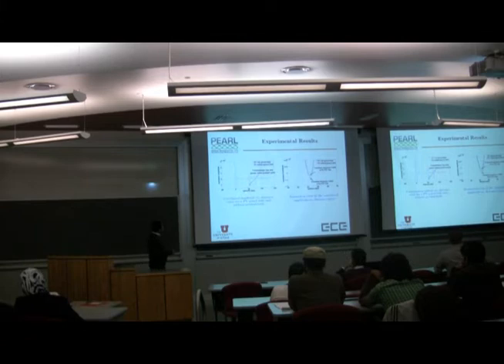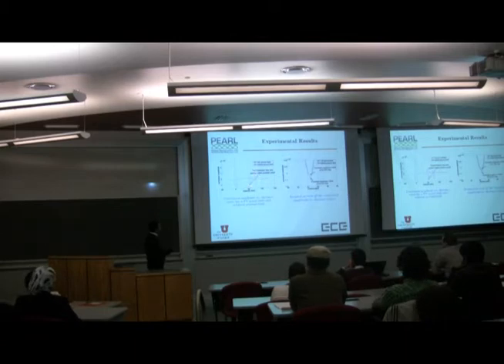This is the result we found, the correlated output, following the equation shown in an earlier slide: amplitude versus distance information coming out of the SSTDR hardware. There are actually two results, PV with ground fault and PV without ground fault, but it shows just one graph, so apparently there's no difference. But if you zoom into that point, you see they are actually different.